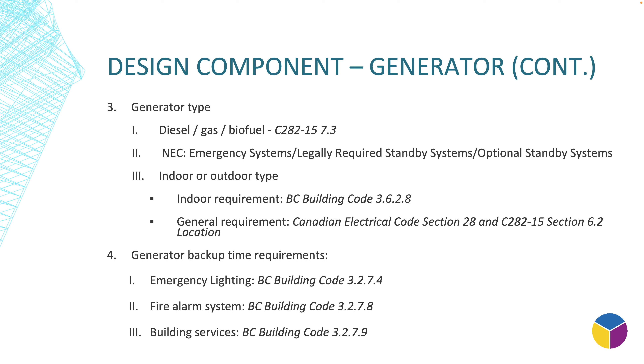Generator type, based on the fuel you use, can be diesel, gas, or bi-fuel — meaning you can use both gas and diesel. In the American National Electrical Code, there are clear categories like legally required standby and optional standby systems, but in Canada we don't have such classification. The generator can be installed indoors or outdoors — if outdoors, we normally specify a weatherproof enclosure with everything in one unit.